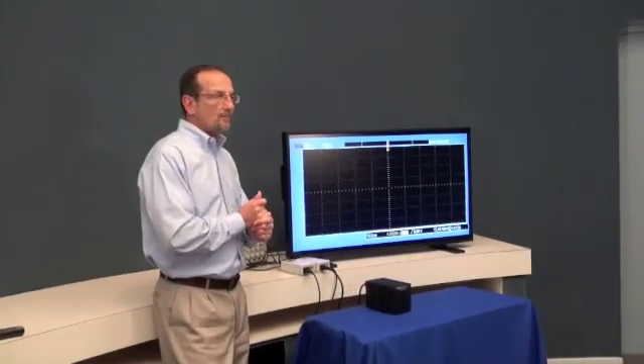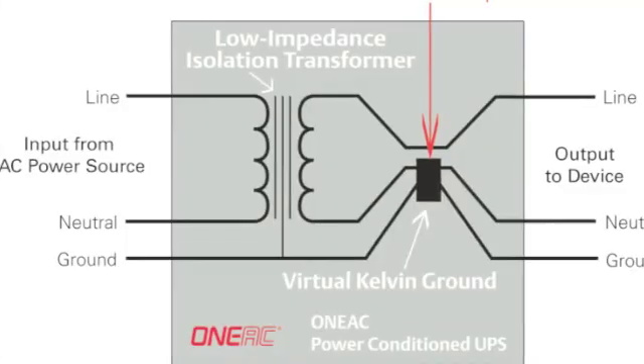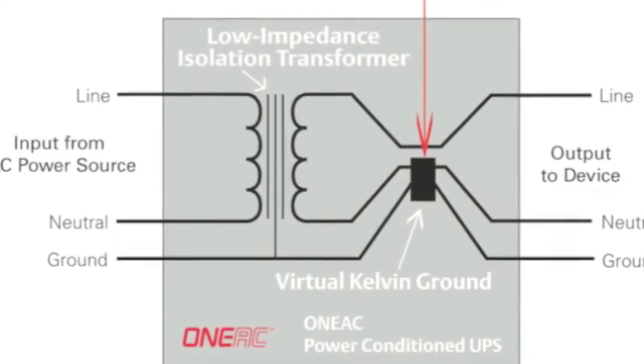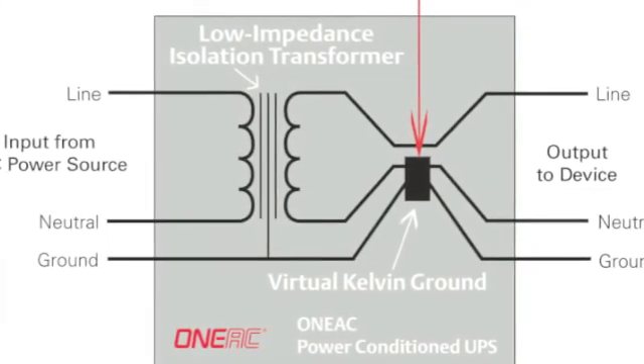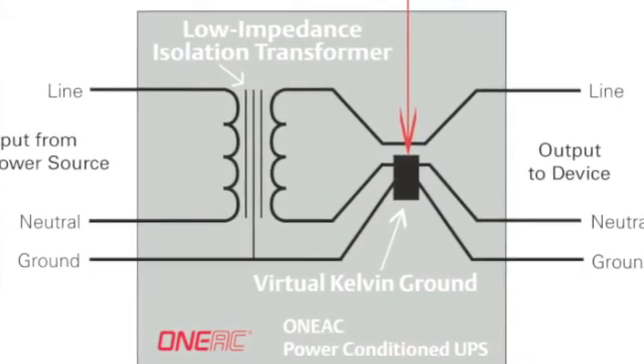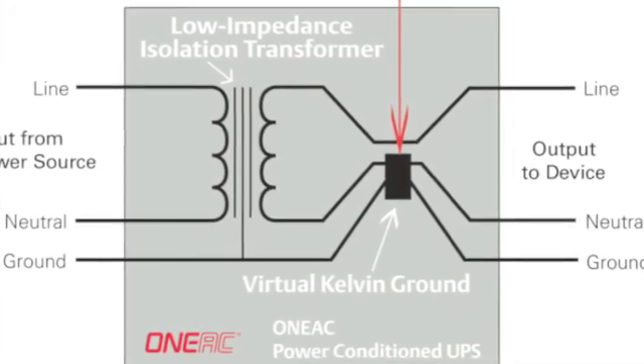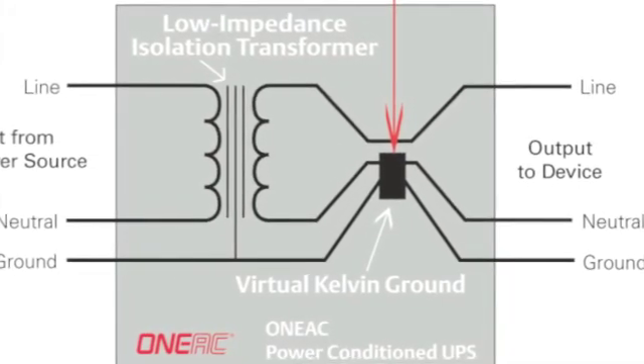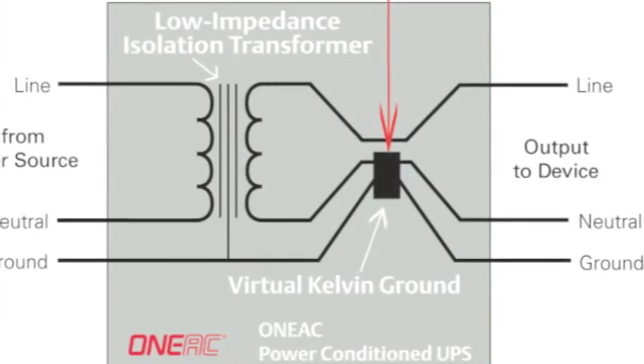So what do we do about those? Here at ONEAC, we have a power conditioner, which is an isolation-based, transformer-based power piece of equipment that regenerates or reconnects the neutral and ground line on the secondary side. So it regenerates your neutral ground bond. That will alleviate a lot of noise situations we're seeing.